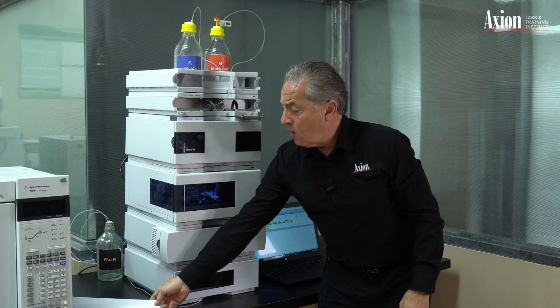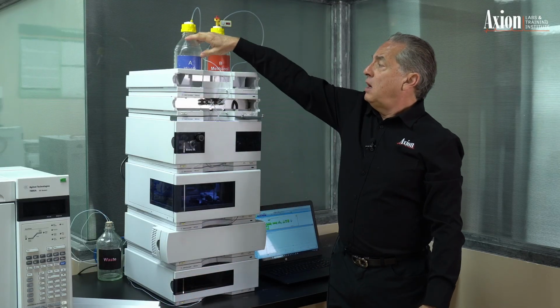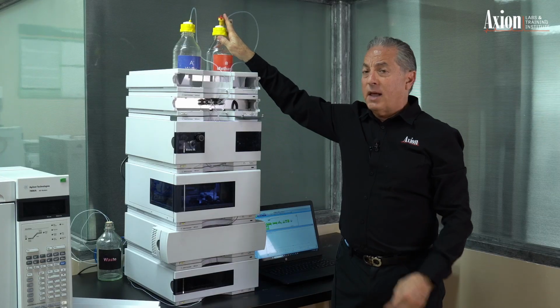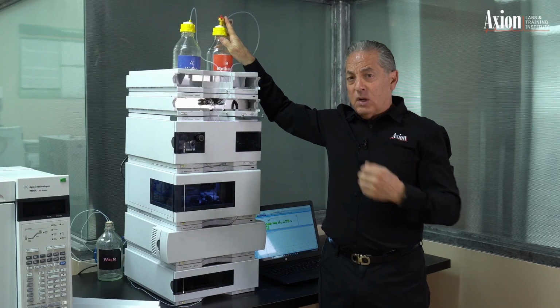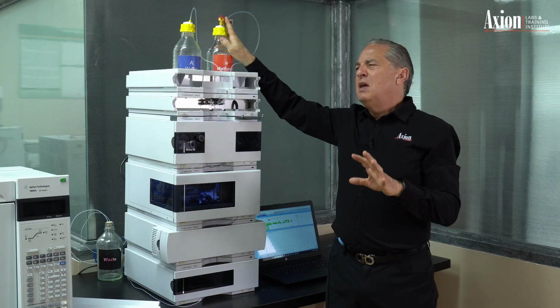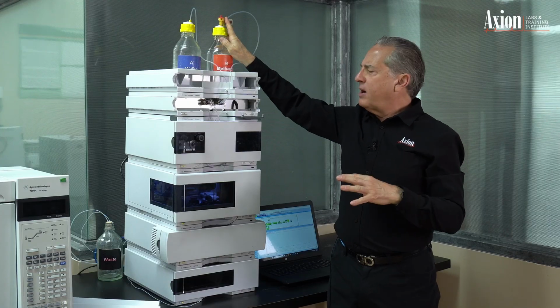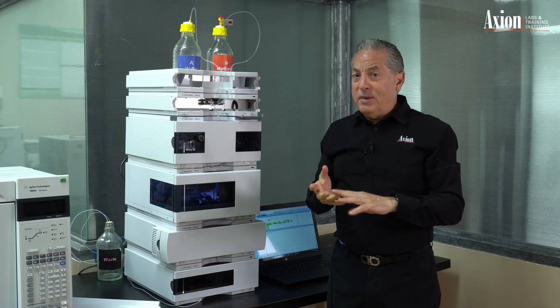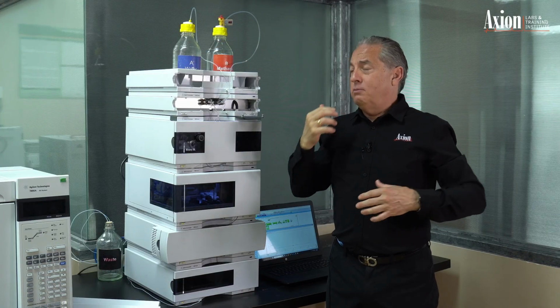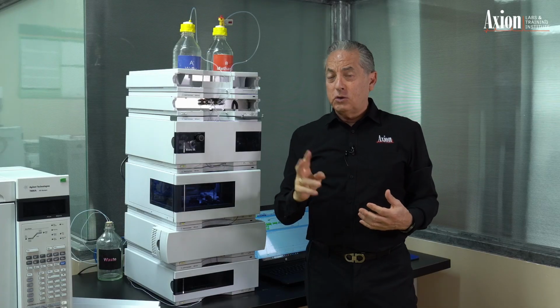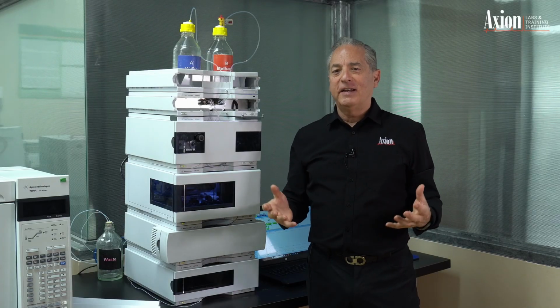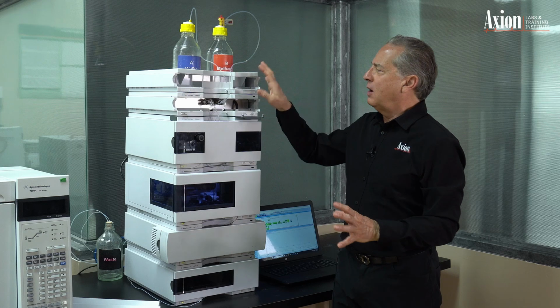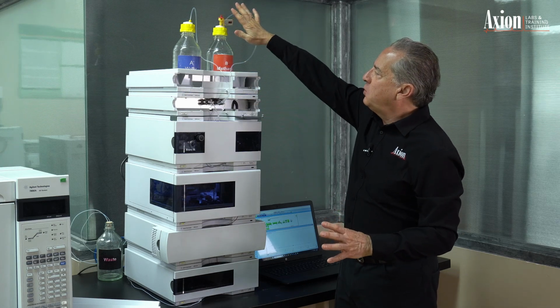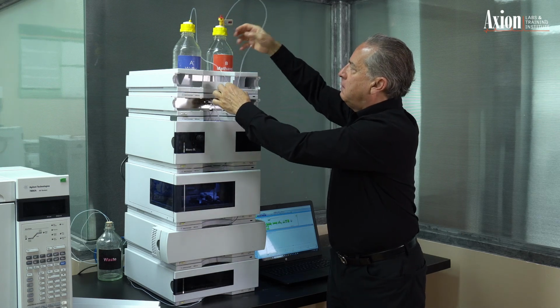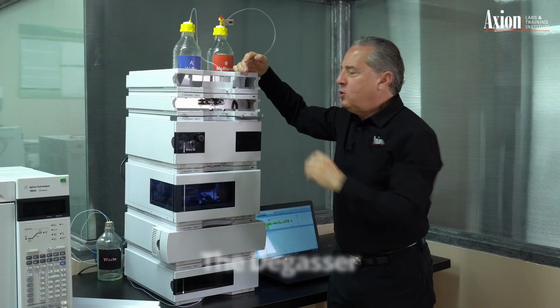So we have our mobile phase. Now some pumps can handle up to 4 solvents, our quaternary pumps. We have about 12 HPLCs. About half of them are quaternary, half of them are binary. So we could have A, B, C, and D solvents. In most cases, you're going to use 2 solvents, A and B, and that's it. We could use others, but typically A and B. And so we have these coming from the bottle itself, and we're going to go into a degasser.